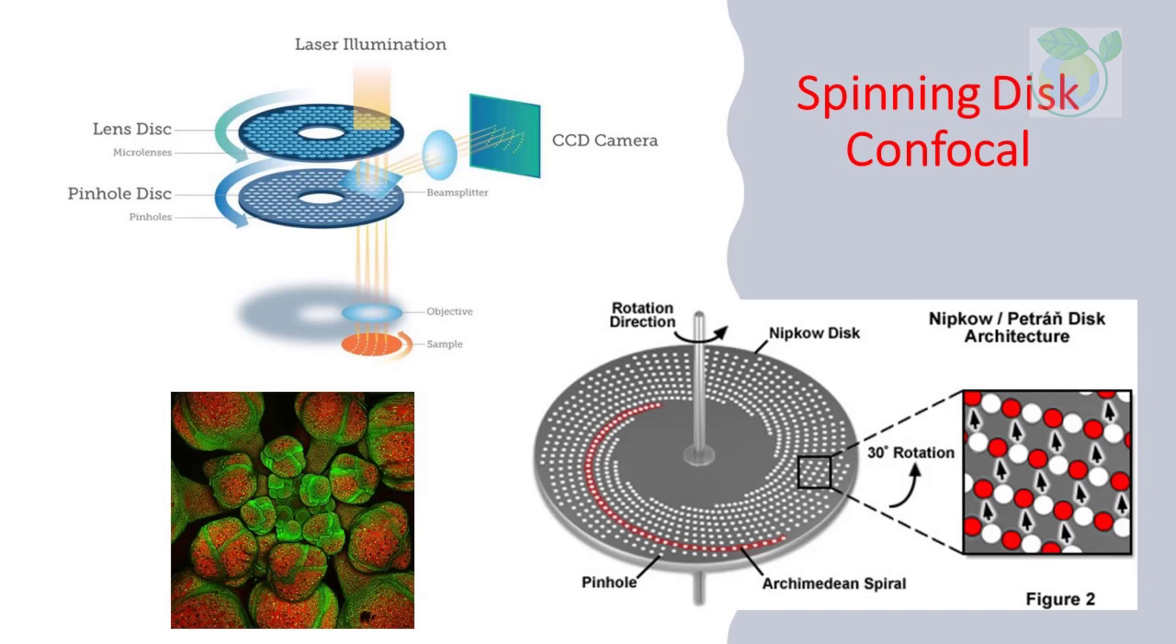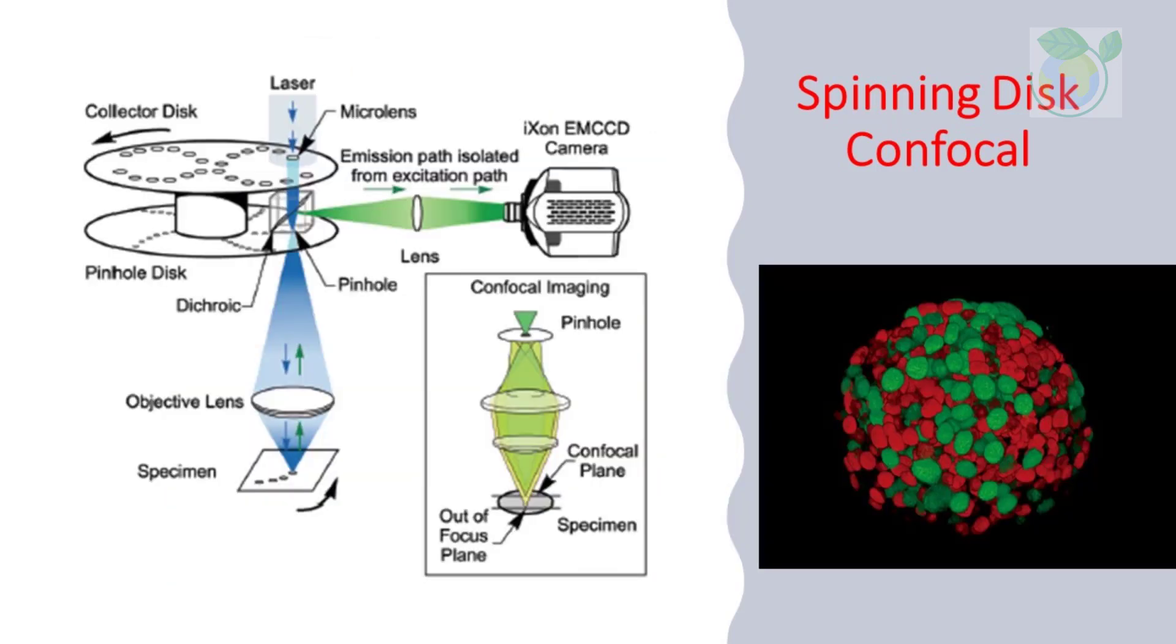Within the spinning disk confocal microscopy, there is an improved microlens enhanced or dual spinning disk confocal microscope that works under the same principles as spinning disk confocal microscopes, except a second spinning disk containing microlenses is placed before the spinning disk containing the pinholes. Every pinhole has an associated microlens. The microlenses act to capture a broad band of light and focus it into each pinhole, significantly increasing the amount of light directed into each pinhole.